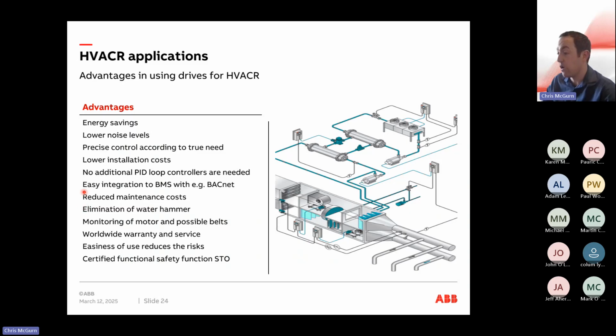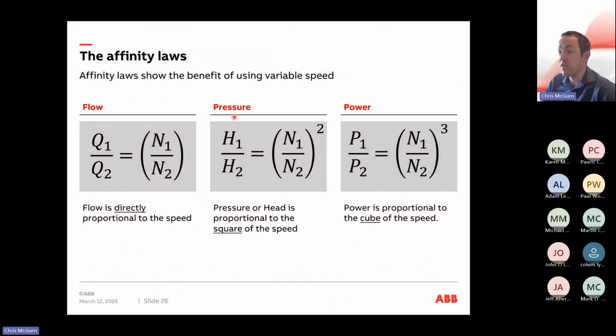You're reducing maintenance costs by using VSDs. By lowering the speed, you're lowering the temperature on the motors. By lowering the temperatures on the motors, the bearings on the motors don't need to be checked as often, and in general you're increasing the lifetime of your motors. And then there are several other advantages, but the main thing in this case is efficiency. That's the main thing we point towards: energy savings with a VSD system.